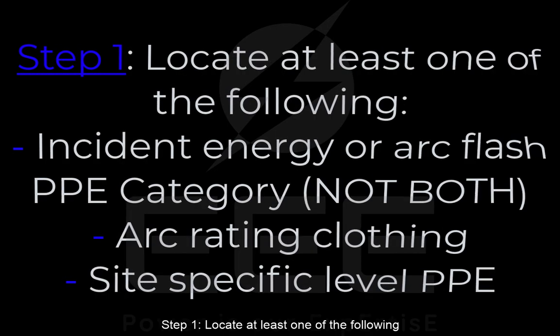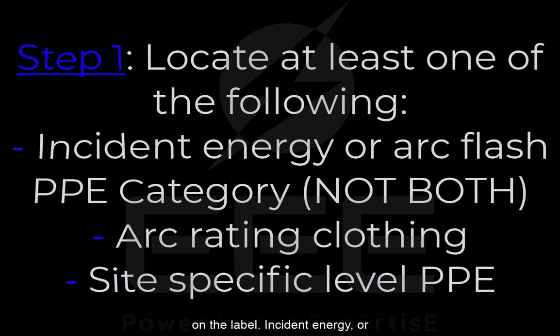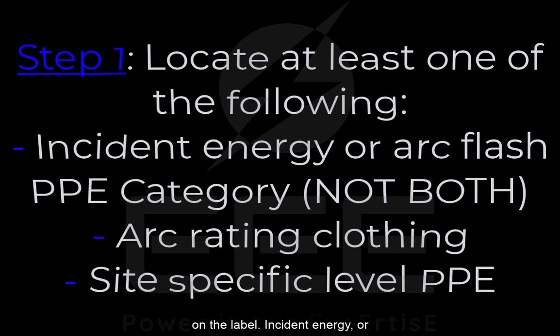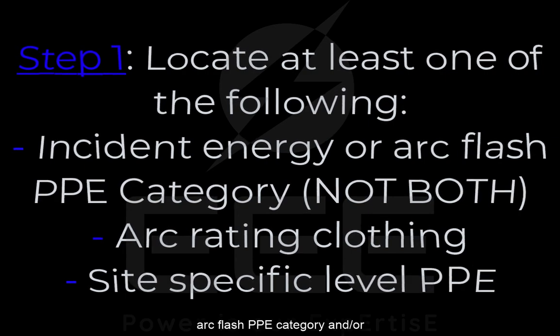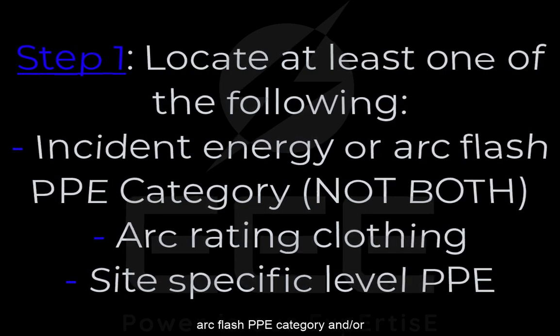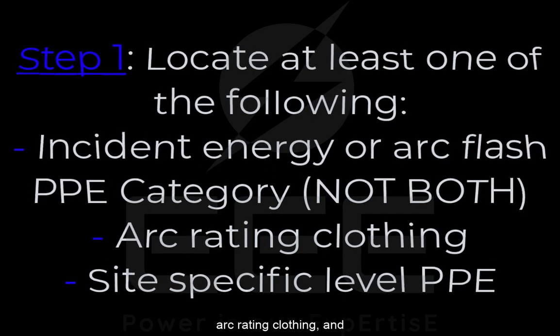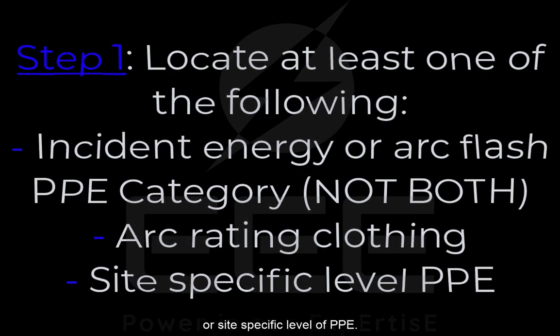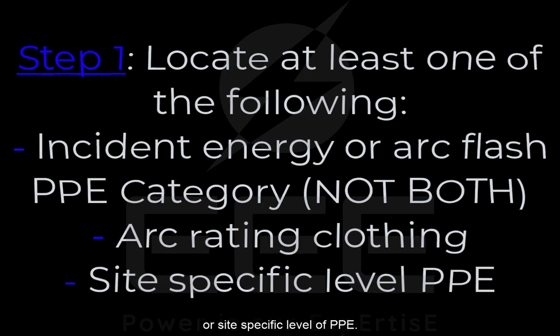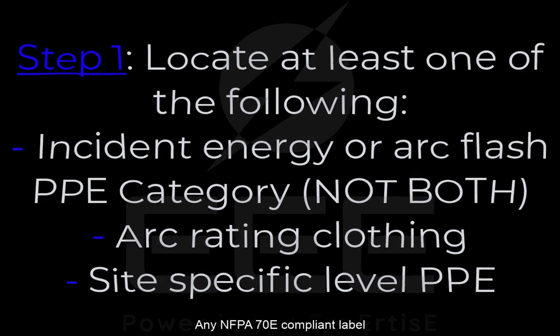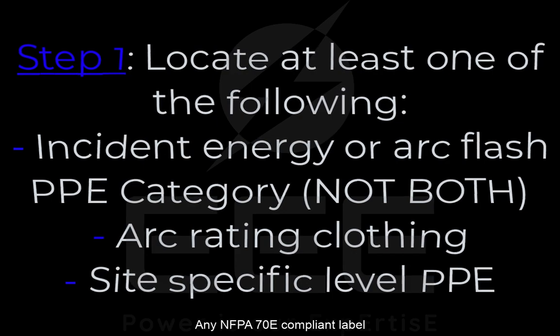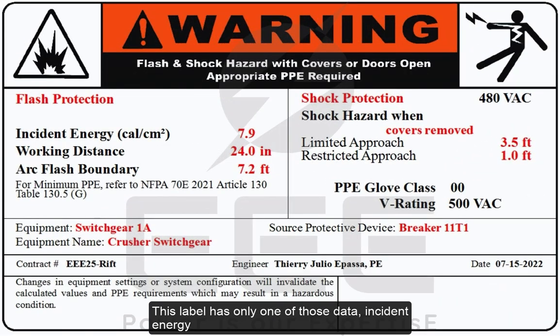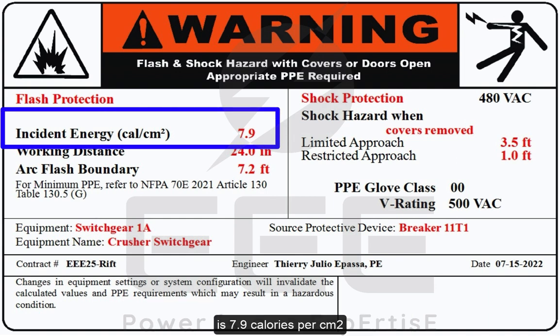Step 1. Locate at least one of the following on the label: incident energy, and/or arc flash PPE category, and/or arc rating of clothing, and/or site-specific level of PPE. Any NFPA 70E compliant label must have at least one of those data. This label has only one of those data. Incident energy is 7.9 calories per centimeter squared.